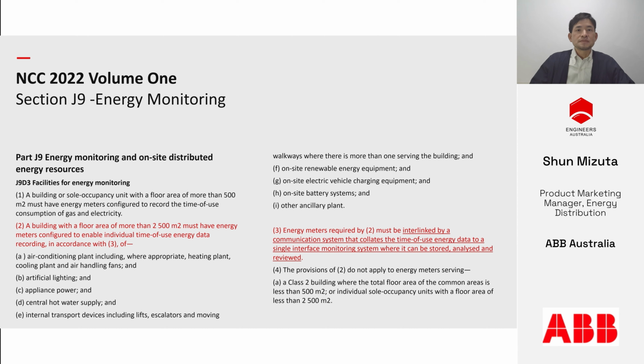Energy meters must be interlinked by a communication system that collates the data to a single interface monitoring system where it can be stored, analyzed, and reviewed. The key point here is that the EMS has to not only gather the energy usage data from the field device, but also locally store, visualize, and present it to a single interface.